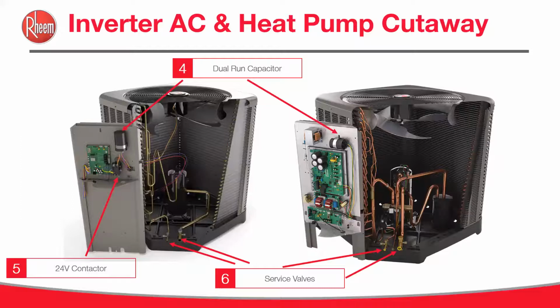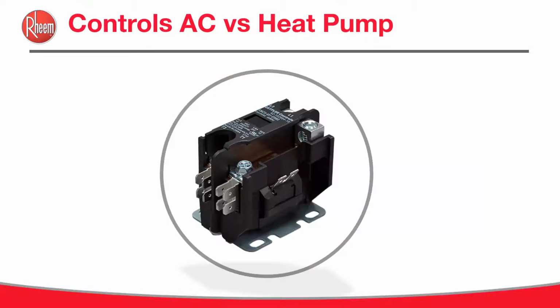So even though the AC and heat pump units both come as inverter systems, the controls are more complex for the heat pumps. As you see here on the left, we've got a little board for the AC system. Still have your dual run capacitor and 24-volt contactor. But when you get into the heat pump systems, it's more complex. It now has a variable speed outdoor board for the fan, and then your main control board. So as we said, controls for ACs versus heat pump. An AC may have something as simple as a standalone contactor to power the outdoor unit.